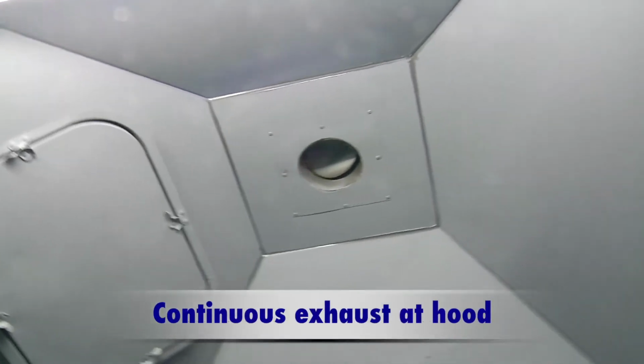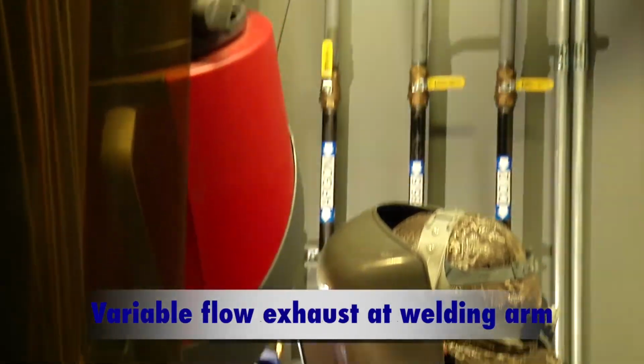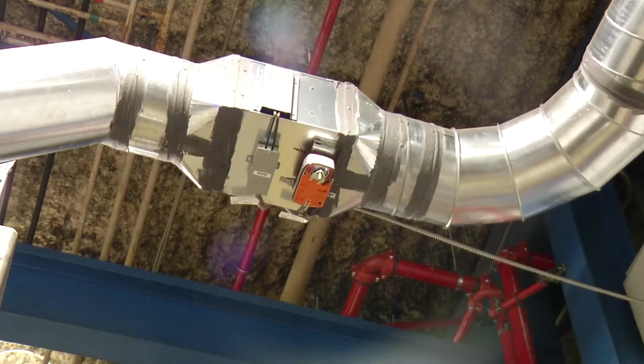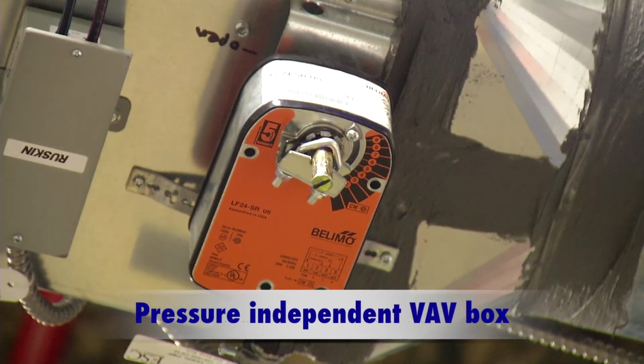Okay, well, in addition to the variable flow exhaust that we've talked about, the welding booths also have continuous exhaust. And essentially what we do is we provide continuous exhaust at the hood and variable flow exhaust at the welding arm. Now, in order to maintain that continuous exhaust at the hood, you can imagine that as all the dampers are opening and closing, the velocity in the ductwork is changing quite erratically. And the way that we maintain constant flow to all the exhaust hoods is with a pressure-independent VAV box up here. And what that box does is, as the flow is changing, it automatically adjusts the airflow to maintain the correct volume at all the exhaust hoods.